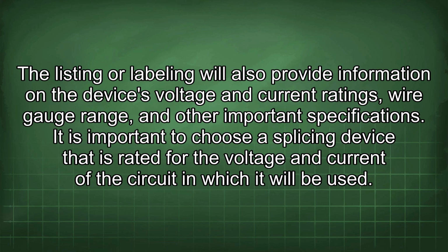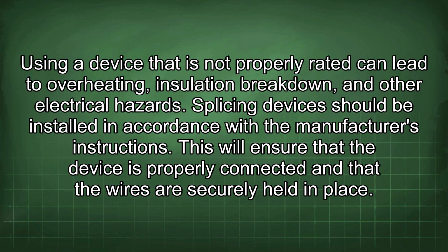The listing or labeling will also provide information on the device's voltage and current ratings, wire gauge range, and other important specifications. It is important to choose a splicing device that is rated for the voltage and current of the circuit in which it will be used. Using a device that is not properly rated can lead to overheating, insulation breakdown, and other electrical hazards.